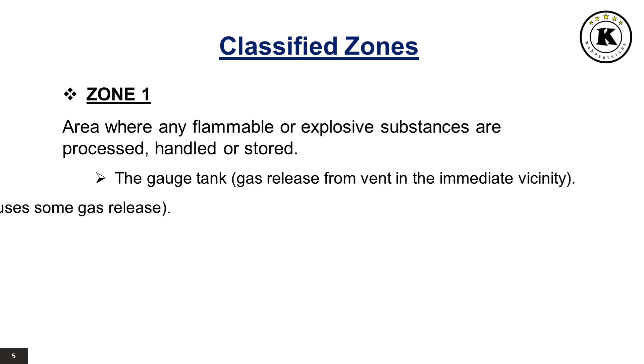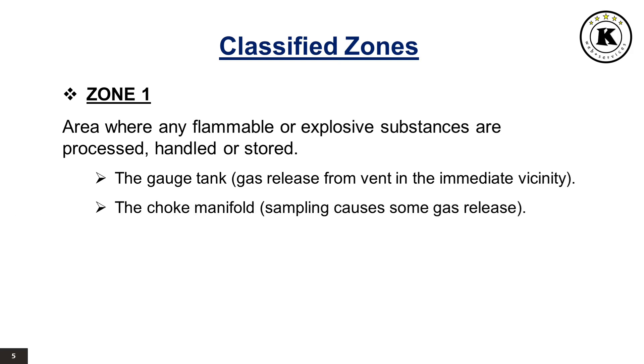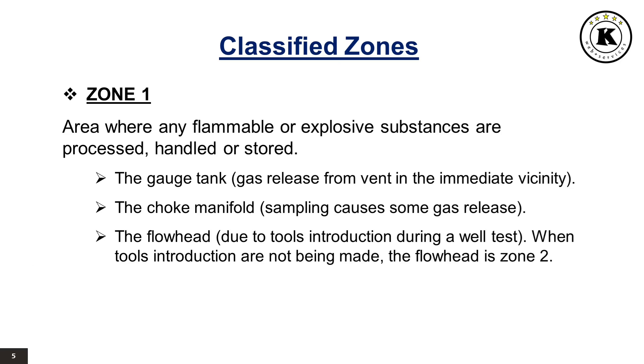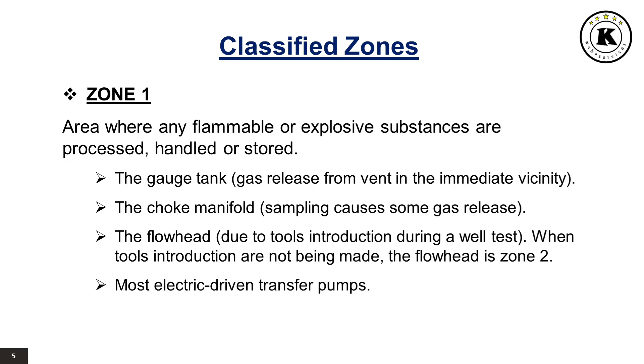The choke manifold is Zone 1 because sampling causes some gas release. The flowhead is Zone 1 due to tool introductions during a well test; when tool introductions are not being made, the flowhead is Zone 2. Most electric-driven transfer pumps are also Zone 1.